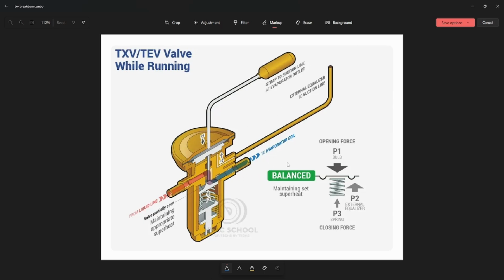That's a TXV. A TXV is strictly mechanical, no electronic components, and TXVs are slow to react, which is why we don't want to use them in some instances. So with TXVs being mechanical and taking time for changes to take effect, they're slow. It's a slow way for us to control superheat, which is fine for single stage systems or even two-stage systems where we don't have that constant shift or that constant modulation in compressor capacity, in system capacity. So with a TXV, again, slow to react, takes time. It's not an instant change with them.